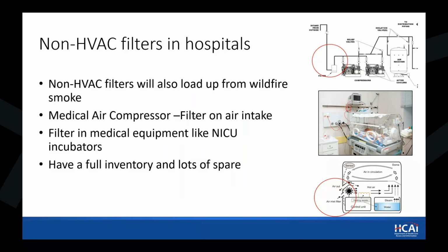Now, when we talk of filters, a lot of people really just focus on HVAC, but there are more than HVAC filters in buildings, especially in hospitals. And I remember when we had the wildfire smoke back in 2020-21, there was a hospital that actually lost their medical air just because the filter on the intake of the compressor was clogged with wildfire smoke very quickly, and they could not find a replacement. So this is why we recommend you have ample spares of those filters, and you can even have a duty standby filter on the air intake.